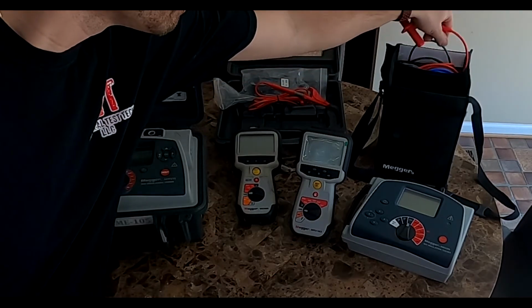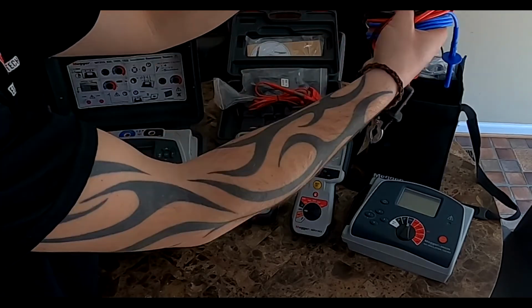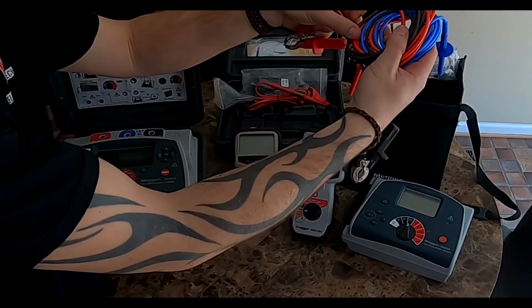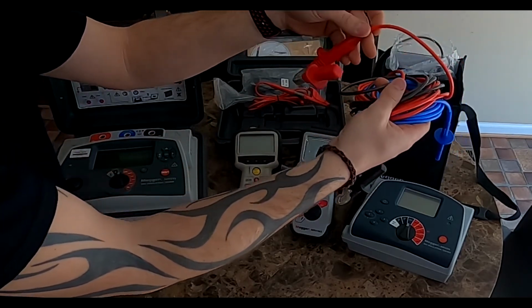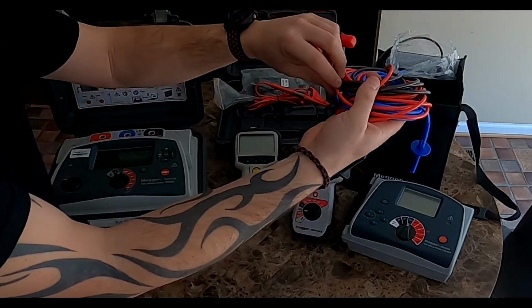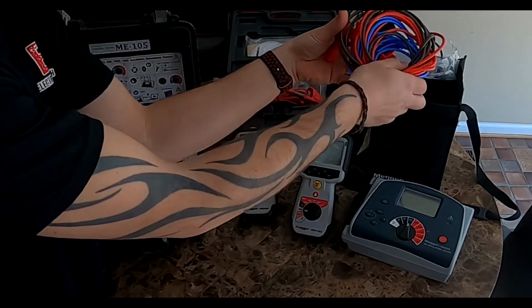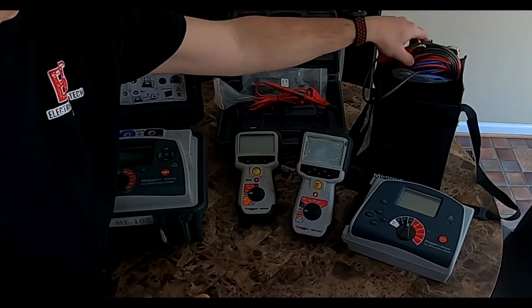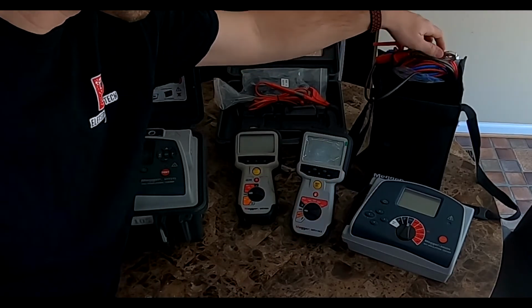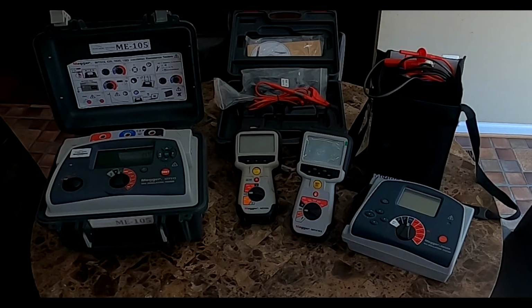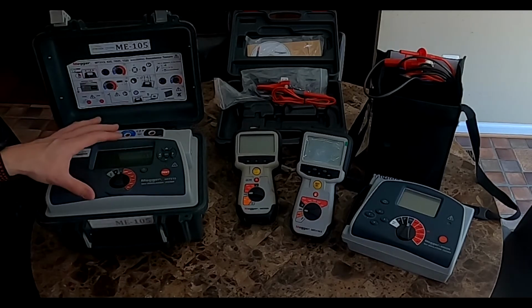Here you have the same silicone leads, except these are the 5,000 volt model, which are rated at 12 kV. It's stamped on the cables here. You wouldn't want to use 1,000 volt rated leads with a 5,000 volt insulation tester, because you will definitely have outside influences. But other than that, that's a brief overview.